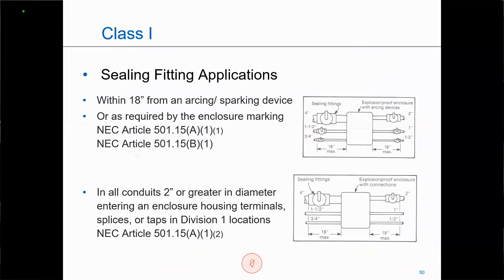Now, when it comes to Class 1 Division 1 and Class 1 Division 1 only, I'm looking at the bottom pictorial now. When I have a product that is housing splices or terminals, I'm required to seal conduits 2 inches or larger. So the top pictorial is arcing sources, both Division 1 and Division 2. The bottom pictorial is only Division 1 splice boxes. Now, the reason that this is not Division 2 also is because, as we saw earlier, if I have a splice box that's in Class 1 Division 2, it's not required to be explosion proof. So putting a seal within 18 inches of that particular non-hazardous rated box gets me no further integrity. So it's not required.